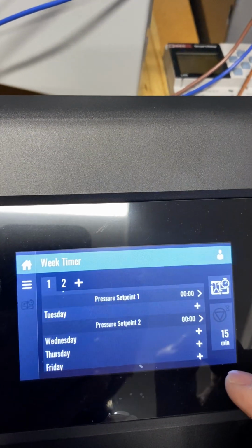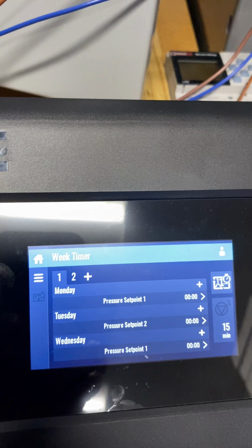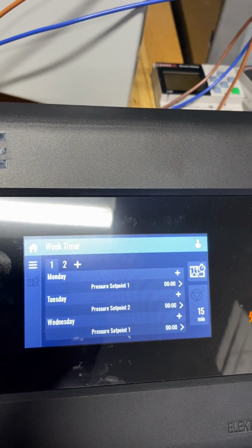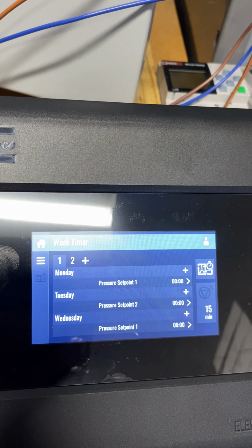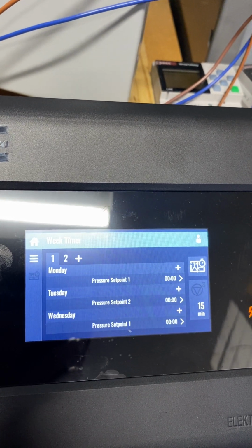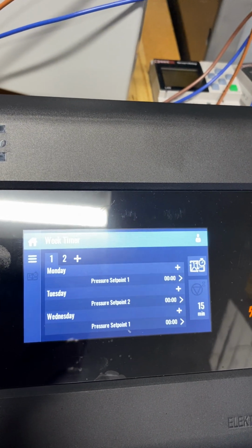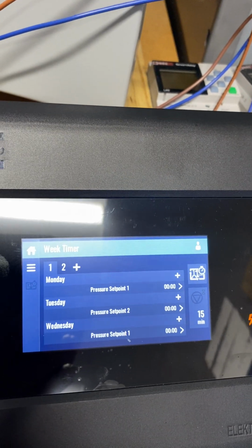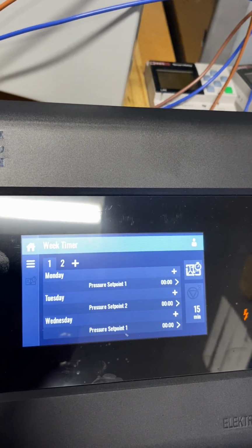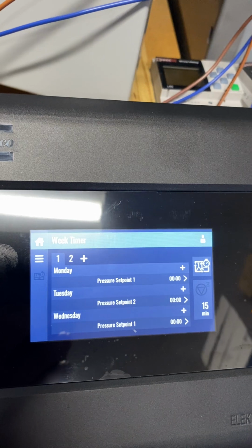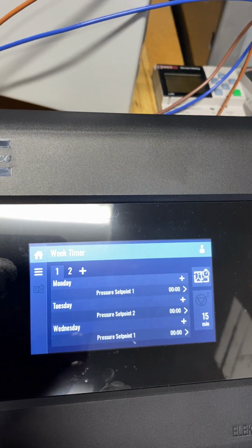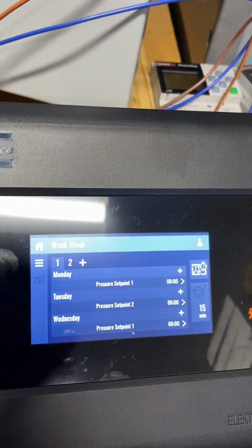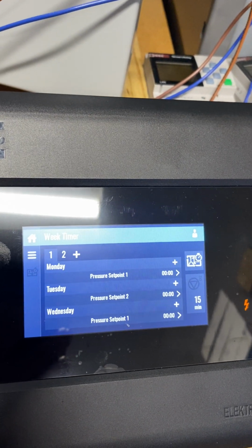Another reason why I chose alternation days is typically the hospital, they will walk around and the engineer will write down which compressor is typically running and the run hour and so on and so forth. So for them not to bug you and call you and say, hey, why is this compressor running 3 days straight with alternation? This is why it's easier to do switching every 24 hours. Of course, you could, in theory, set up to change every week.